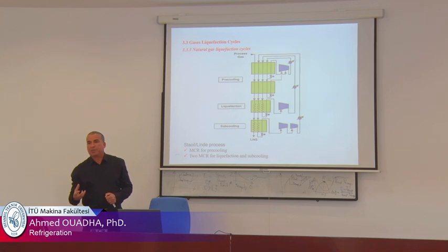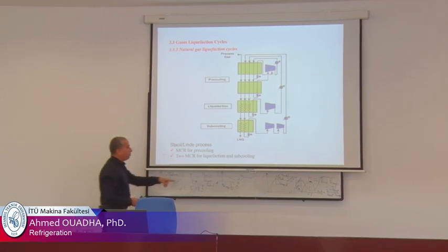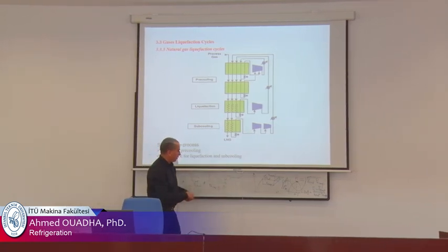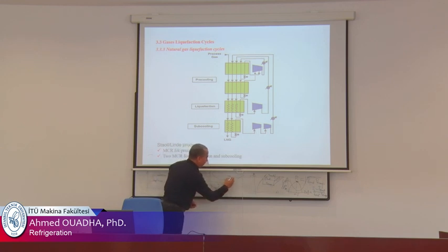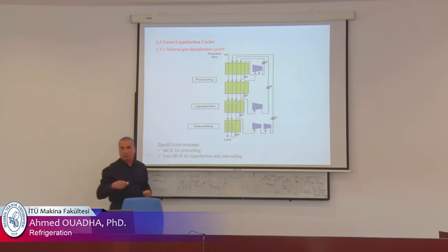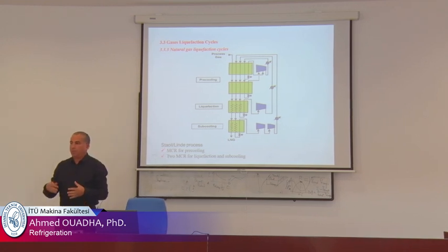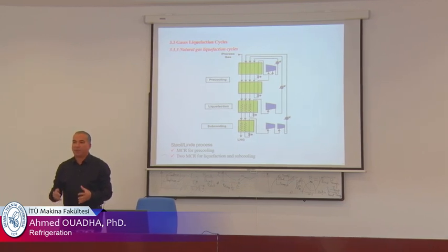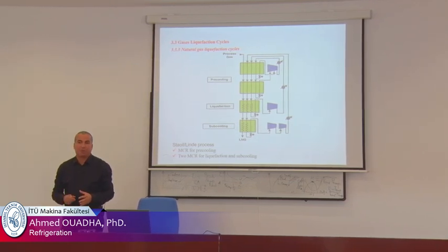This is valid for a pure refrigerant. For a mixture, the temperature may have a glide, maybe like this. The phase change may occur with a temperature glide for some mixtures. But for a pure refrigerant, the phase change is at constant temperature and pressure.